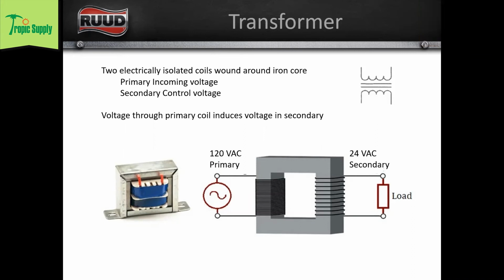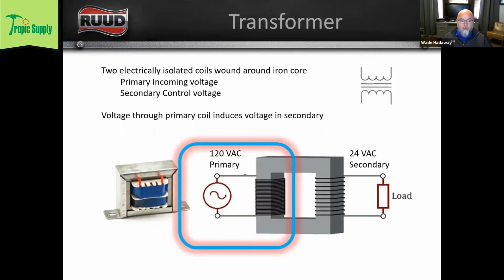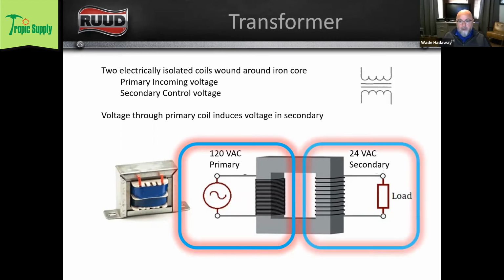Thank you. So a transformer is two coils, right? We've got two electrically isolated coils, and each one of these coils is wound around an iron core. And when voltage passes through our primary, it induces voltage in the secondary, and it does that through a magnetic field. So our 120 volt primary coming into our transformer induces inductive power, meaning that we create an electromagnetic field, and that's the electromotive force that starts the electrons pushing on the 24 volt side, or our secondary.